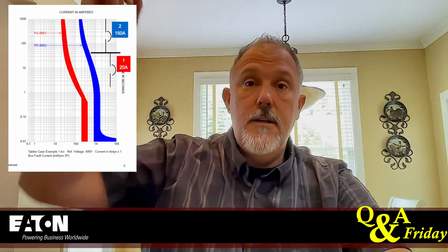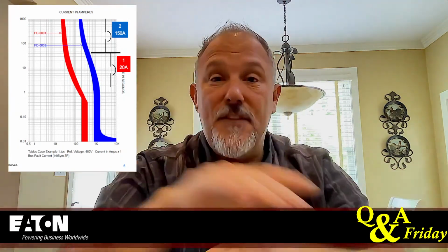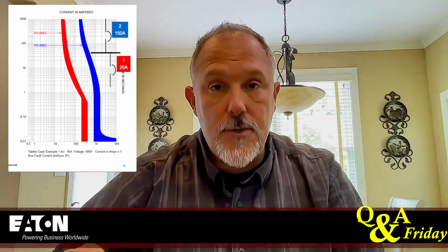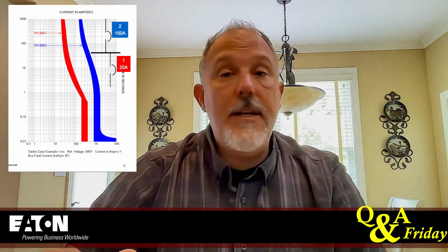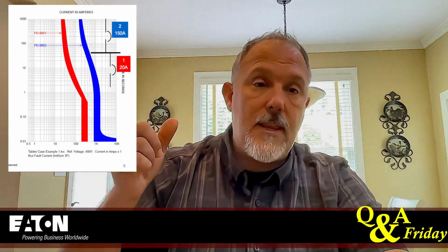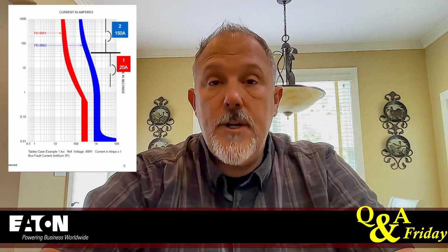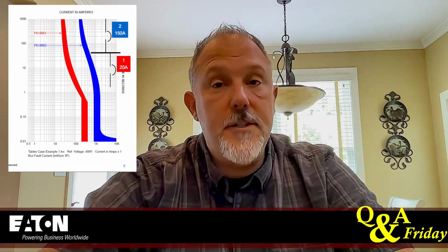Your coordinated system for a ground fault will cause multiple devices to open. Done deal. It could cause your main overcurrent protective device to trip and take the entire facility out. Why? Because you did 0.1 seconds. So yes, you are right. You don't need the tables. You don't even need to calculate fault current anywhere in the system other than to do interrupting ratings. All you need to do is look at the overload region, hide everything below 0.1 seconds, and make sure you have separation of curves. That's all it is. It's like art. Piece of cake.